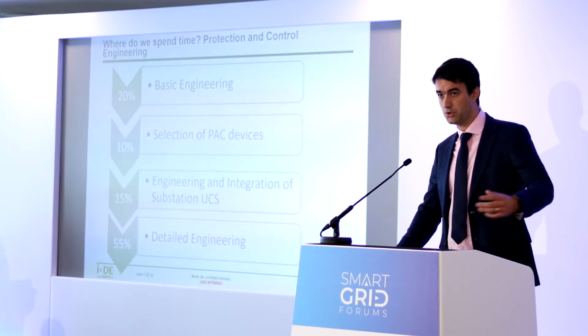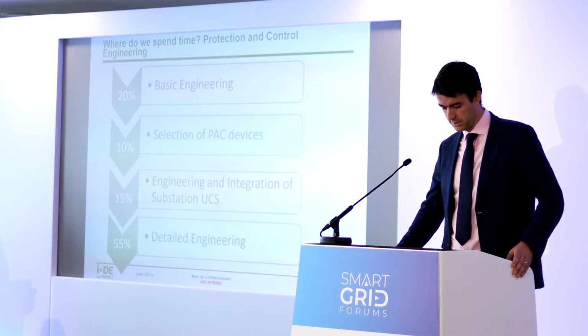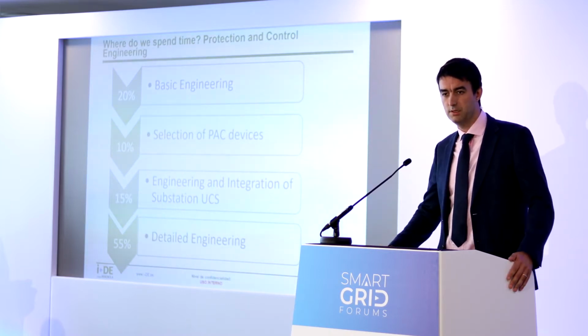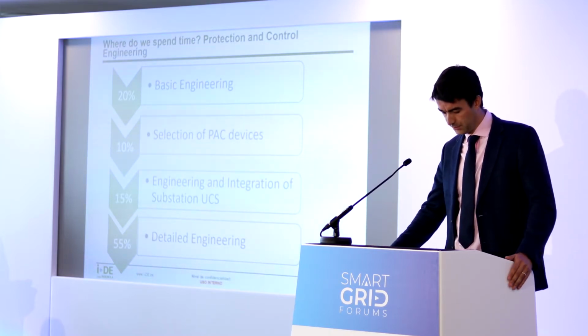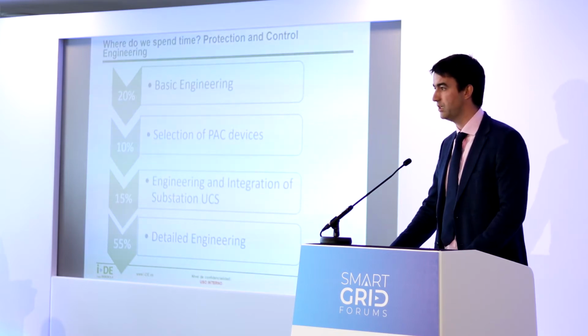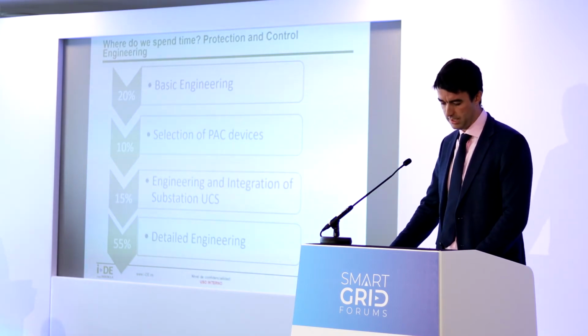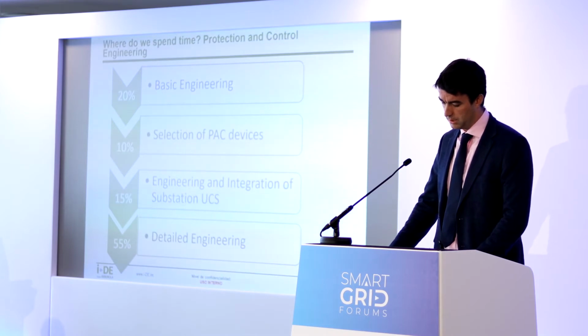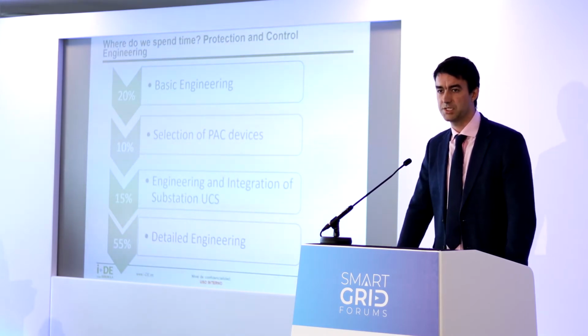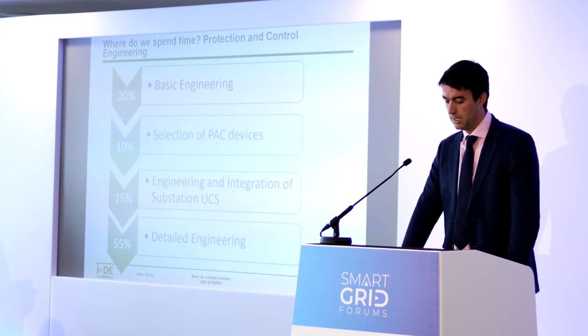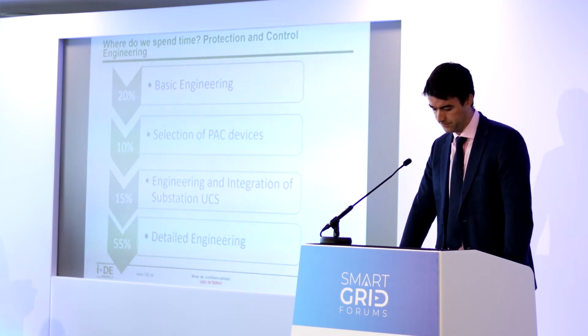And if we were to outsource the loading of that file into the device to the switchgear manufacturer as our system integrator, how would we know that we had loaded the right configuration file into the right IED and not the wrong one? This brings us to the next exercise, which expends a lot of time: device testing.